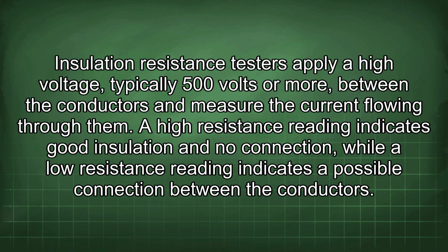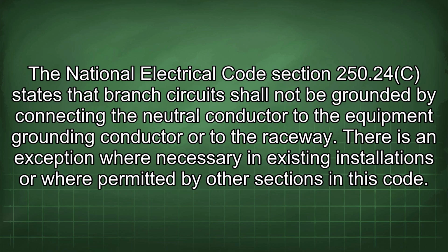Insulation resistance testers apply a high voltage, typically 500 volts or more, between the conductors and measure the current flowing through them. A higher resistance reading indicates good insulation and no connection, while a low resistance reading indicates a possible connection between the conductors.